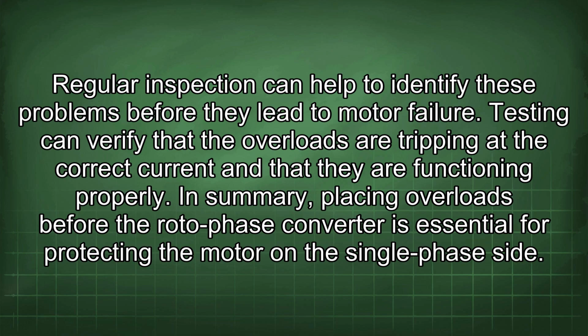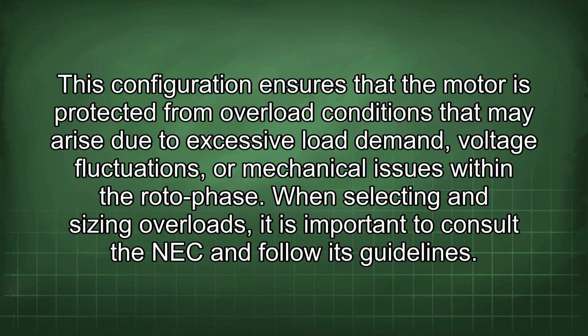In summary, placing overloads before the roto-phase converter is essential for protecting the motor on the single-phase side. This configuration ensures that the motor is protected from overload conditions that may arise due to excessive load demand, voltage fluctuations, or mechanical issues within the roto-phase.